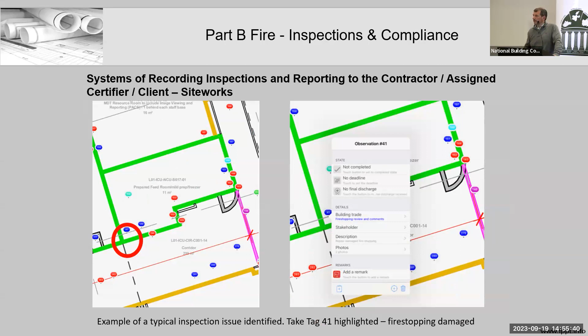I've focused on pin 41 as an example - this was a fire stopping issue. It was identified, a description and details were provided, along with photographs. As you can see, damage was done to the fire stopping and the damper, something that usually happens when ductwork gets installed after the damper. Since it's done as a staged process, the damper was installed and fire stopped, but the subsequent ductwork installation then damaged the fire stopping.